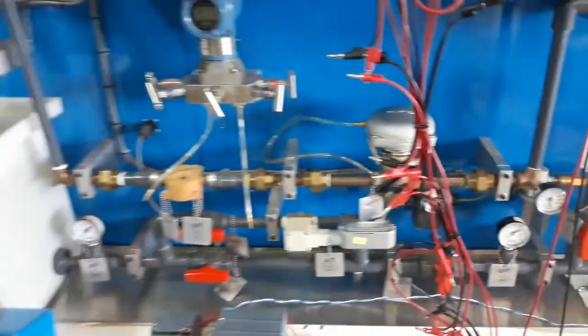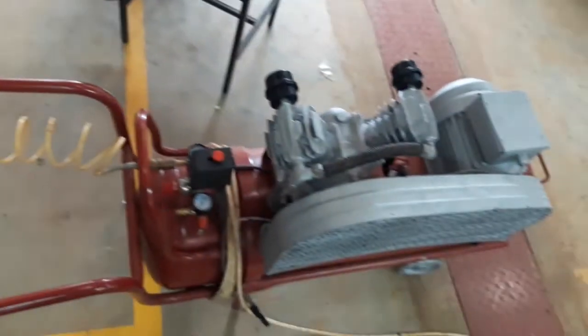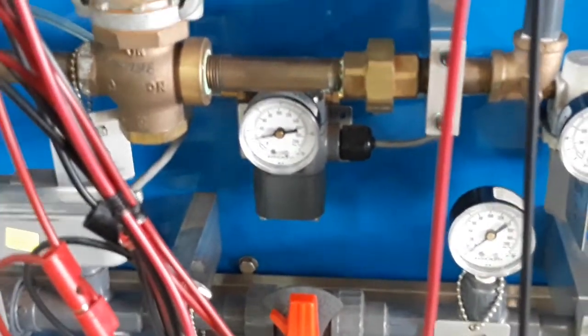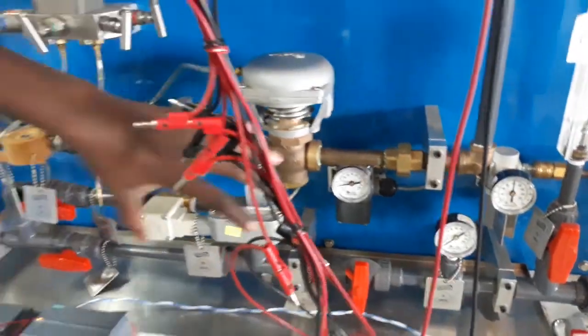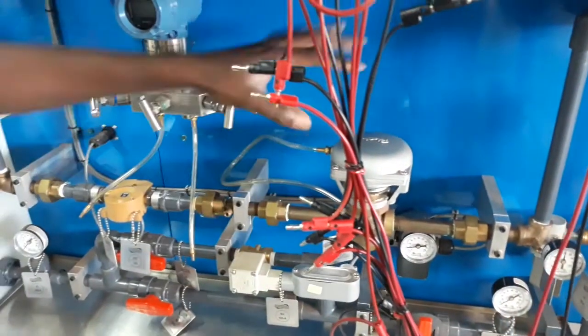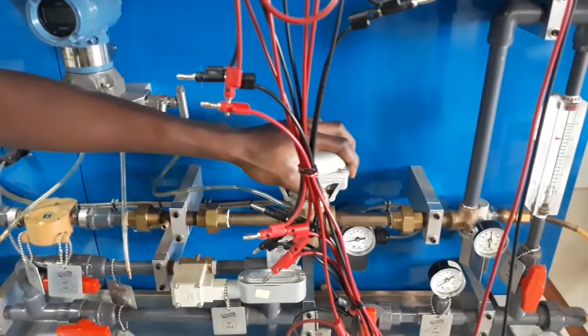For the pneumatic system, it implements a compressor to provide pneumatic control to the diaphragm valve which is controlled by the PID. When it gets a signal from the PID, a current signal, it converts the current signal into a pneumatic pressure signal that is used to control the diaphragm valve.